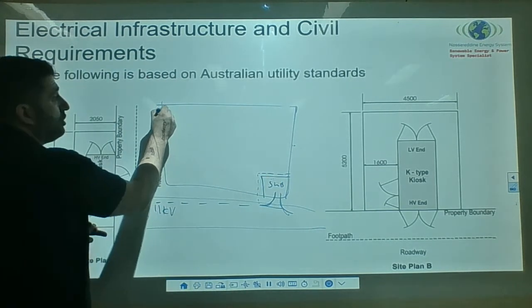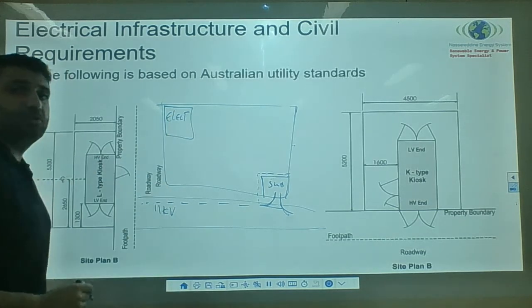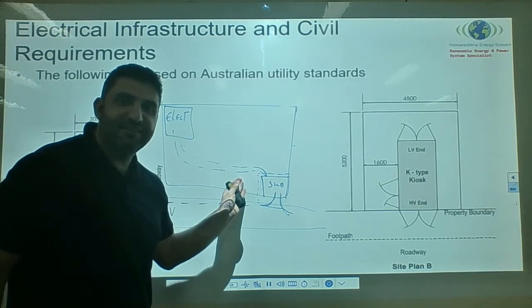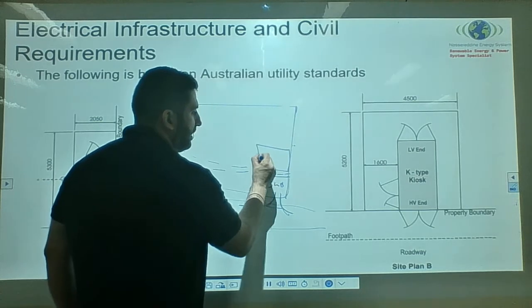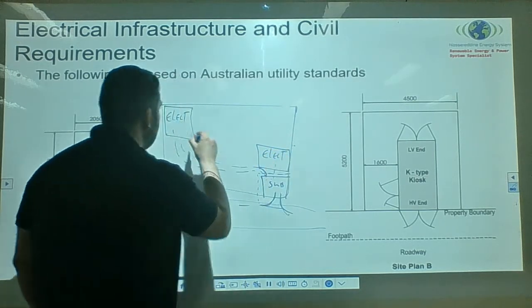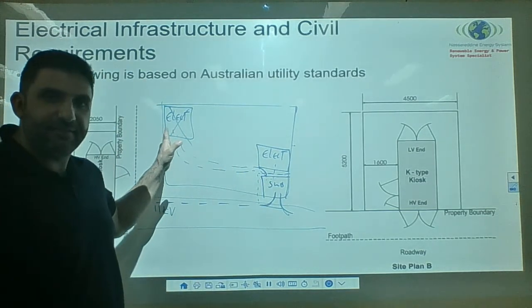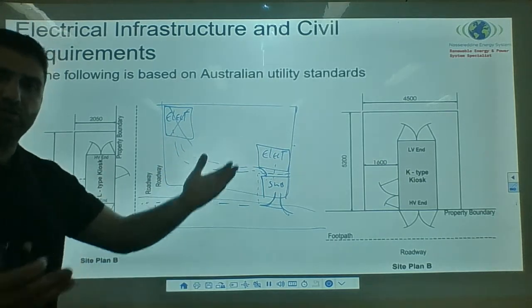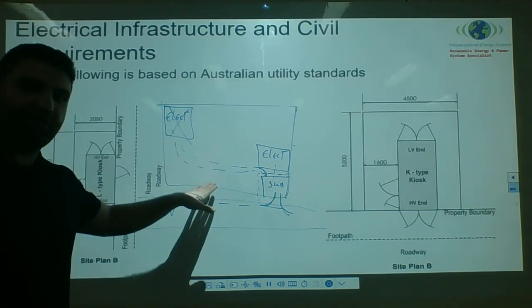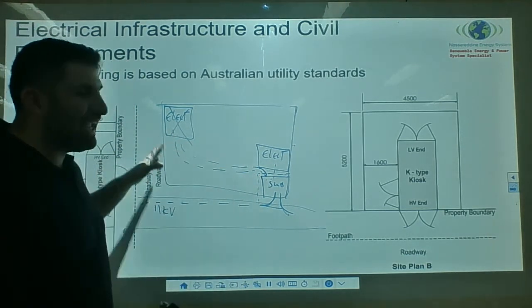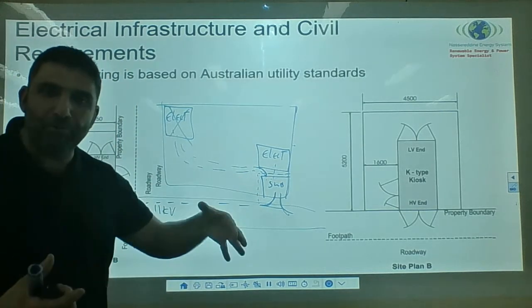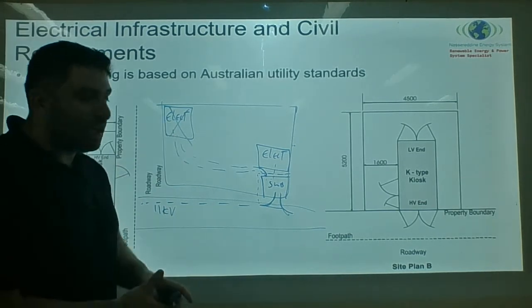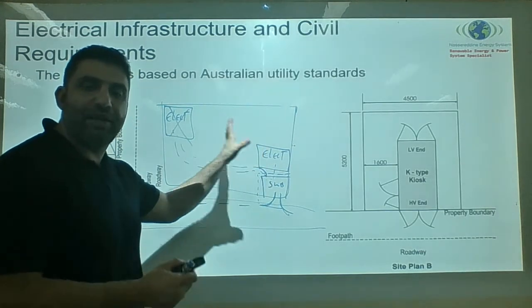When it comes to the low voltage side from the substation, I should have the electric room located close — because high current over long distances requires larger, more expensive cable, fire-rated cable, and creates voltage drop issues. The longer the cable, the larger the voltage drop, the bigger the cable required, the more cost. This all happens just because the electrical engineer did not coordinate with the architect, civil, and mechanical teams at the area planning stage. Early coordination is critical — clearance zones for electrical main infrastructure must be carefully maintained.